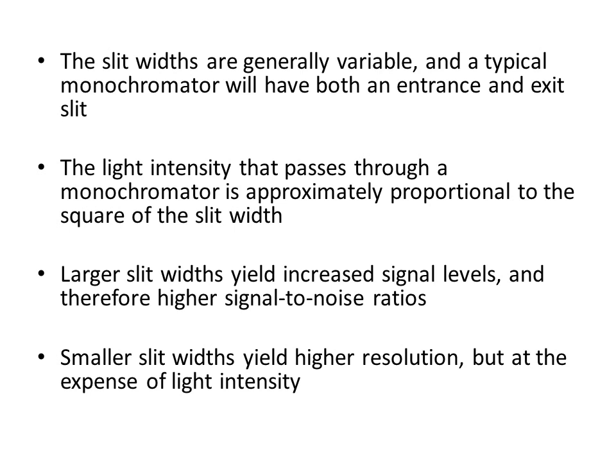Slit width varies according to our needs — sometimes we work on a single wavelength, sometimes on a range. A typical monochromator has both an entrance and exit slit through which light enters and exits. The light intensity passing through a monochromator is approximately proportional to the square of the slit widths — greater slit width means higher intensity.